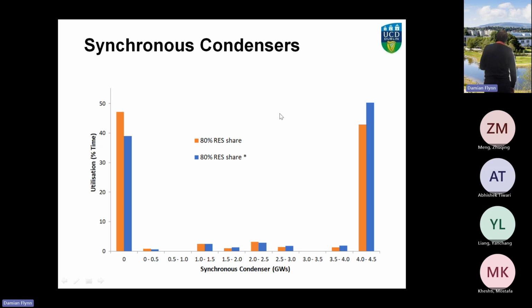What you tend to find is that even when you give the system optimization freedom to use the synchronous condensers, it either says: if it's not windy and not sunny, and I'm using conventional generation, then I don't need the synchronous condensers. But if it is a windy or sunny day, then I'm using all of the synchronous condensers so I can displace my conventional generation.